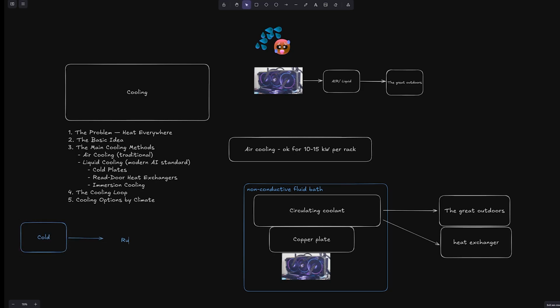For cold climates, we have the so-called free cooling, literally just run the fans. No chillers needed for most of the year. For moderate climates, we have dry coolers with adiabatic spray on hot days. And for hot or humid climates, we have chillers or hybrid systems which consume way more energy. In short, cooling is the lifeblood of an AI data center. It is necessary for day-to-day operations, but is different between each one.